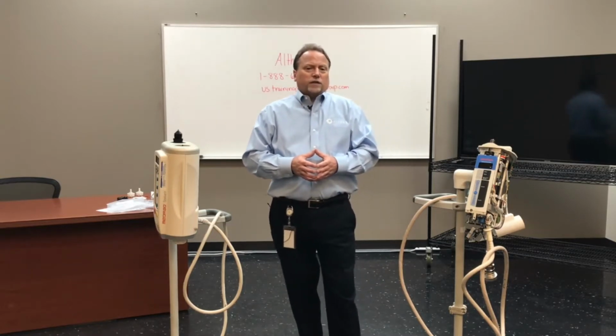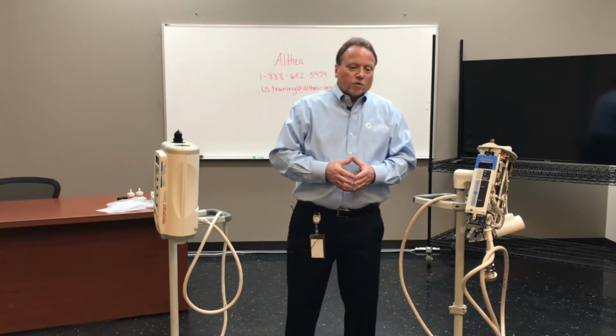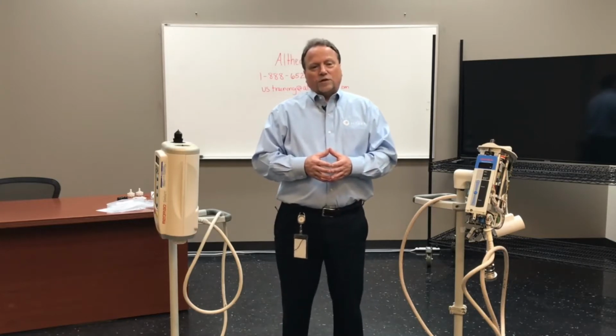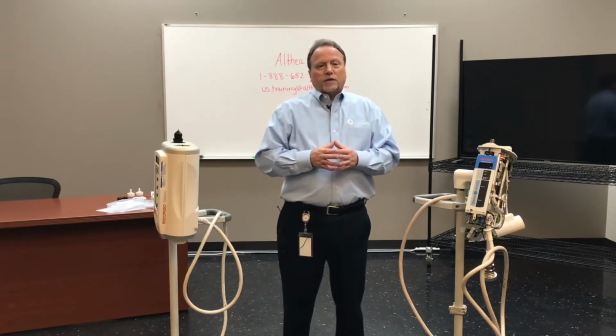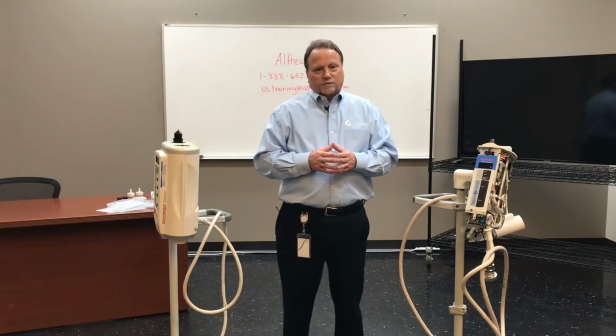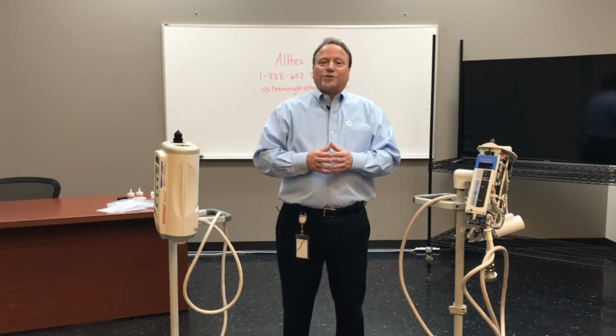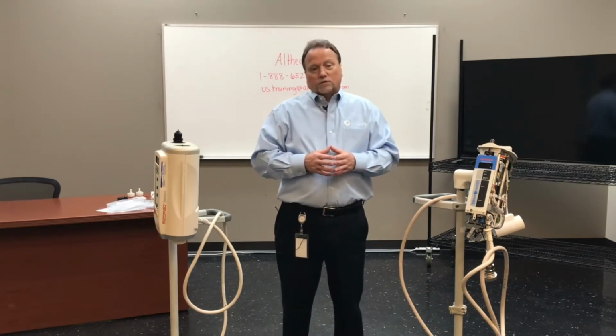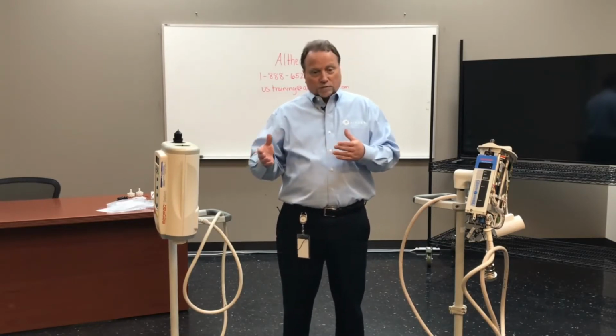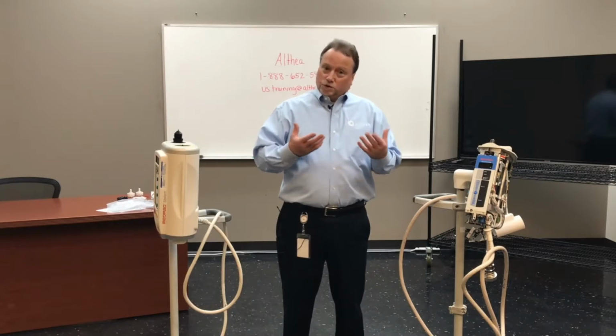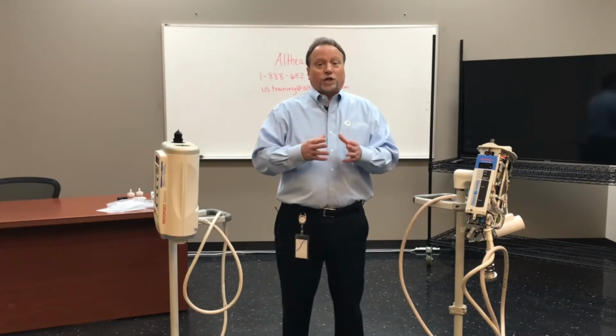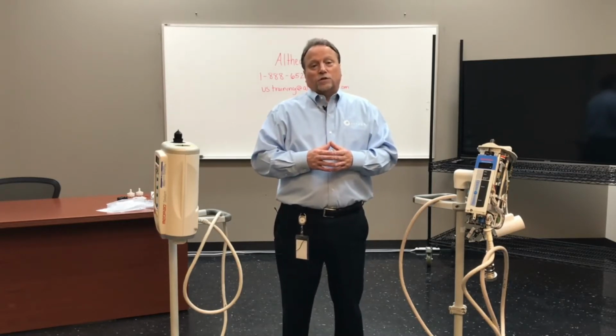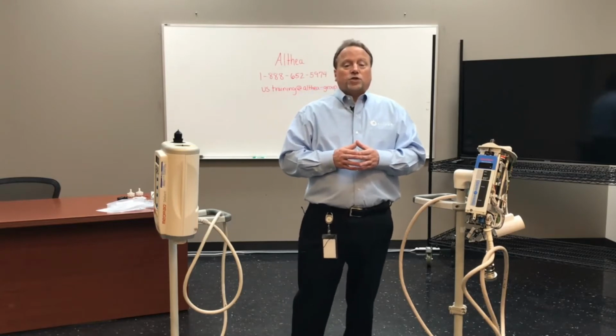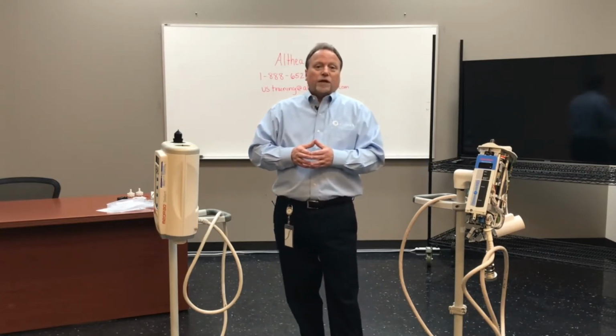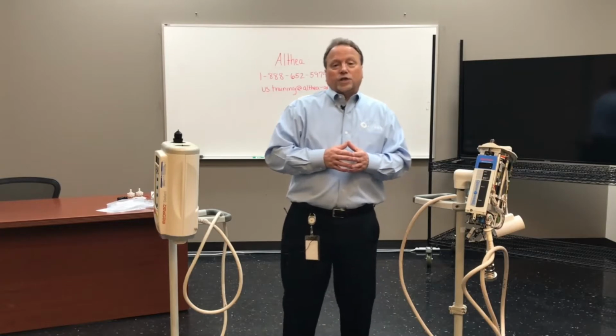How long does it take to do a PM? There are several factors involved, the biggest being how dirty the injector is. Typically, on a typical injector, it's about 2 hours long from start to finish. If you have a contrast-soaked injector, it will take longer, but I usually schedule 2 hours to do the PM and give it back to them.